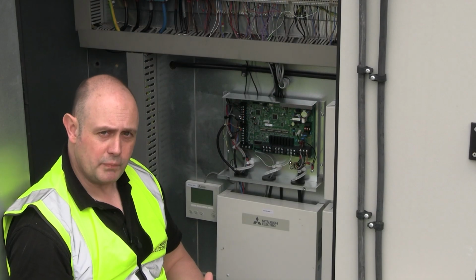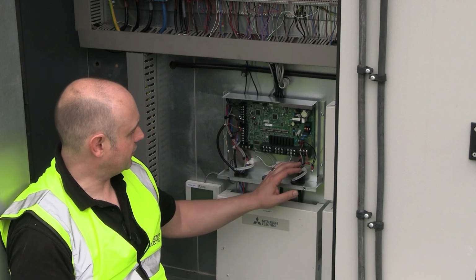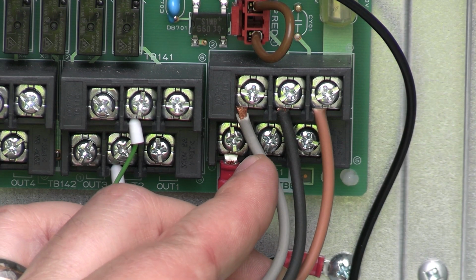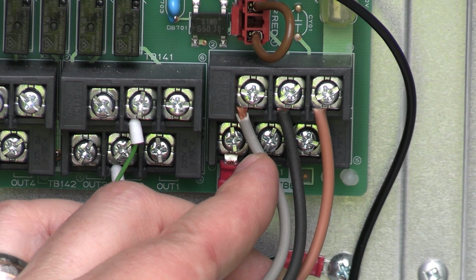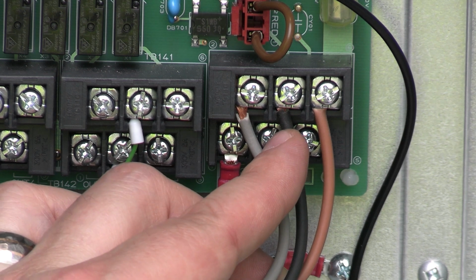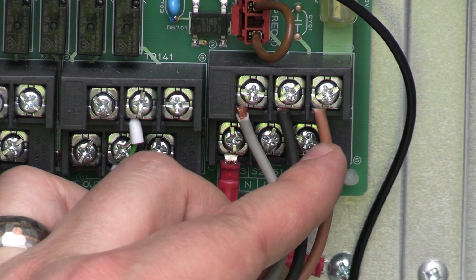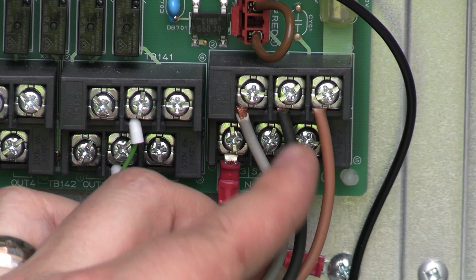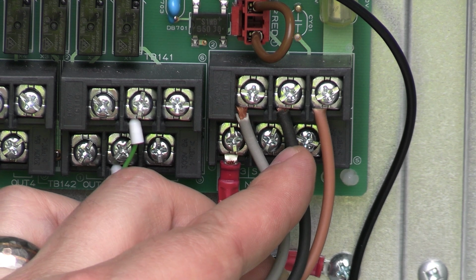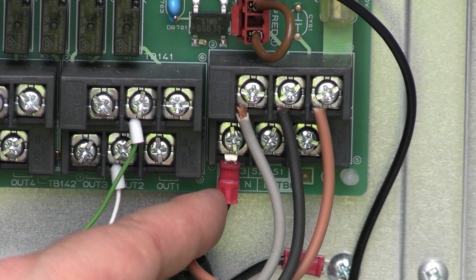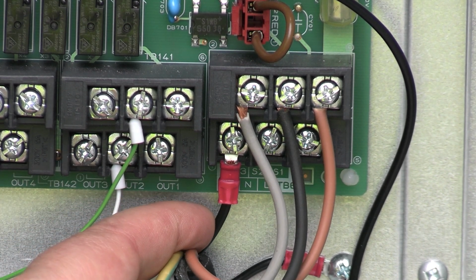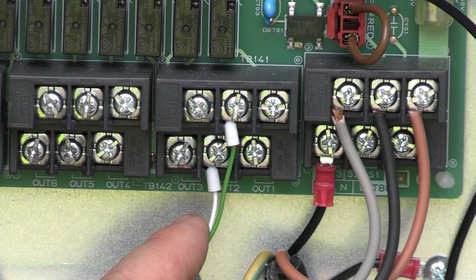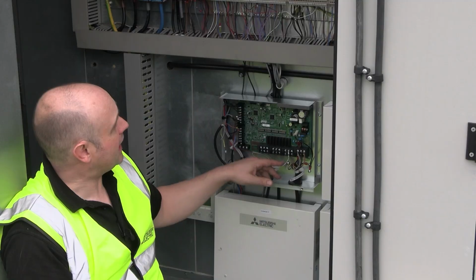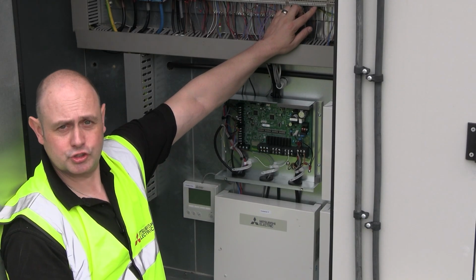So we've got the wiring going from the outdoor unit to the pack IF, and we've got on there S1, which is my live, S2, which is my neutral, S3, which is comms, but S2 is also a negative neutral on the comms side. And underneath there, we've also got that earth connection, so it's just belt and brace to make sure it's all being properly earthed, keeping it nice and safe. We're using out2 as an error output, and that's being fed back to the air handling unit controller.